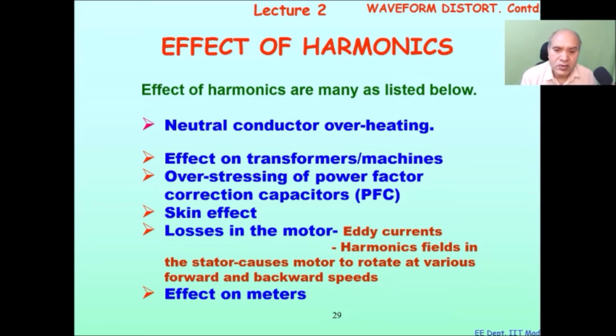The first is neutral conductor overheating. The size of neutral conductors becomes larger when there are harmonics. We can see it in the next slide. Transformers and machines get more overheated and have more losses. Then there is overstressing of power factor correcting devices such as capacitors, which also become a threat to the power system when there are harmonics. Skin effect, that is, high frequency effect on the power conductors. The losses in the motor. At harmonics, the eddy currents and harmonics create more losses in the system.